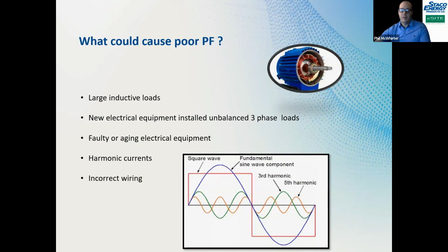How do you know that there's a poor power factor issue? Well, sometimes you really don't know until it's too late. Say you get your monthly utility bill and boom, it spikes up. Well, why did it spike up? That could be because of poor power factor issues. Some utility companies will charge you for poor power factor.